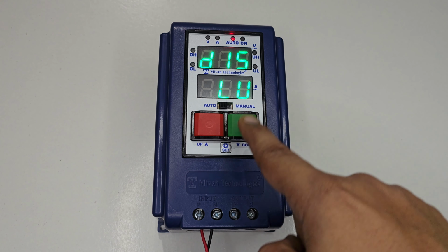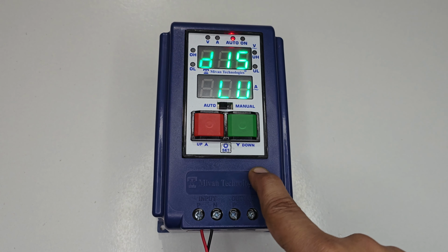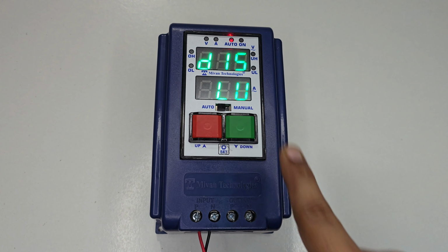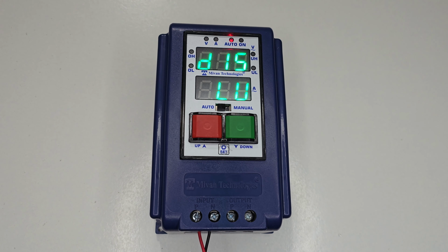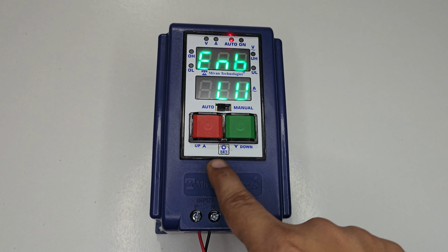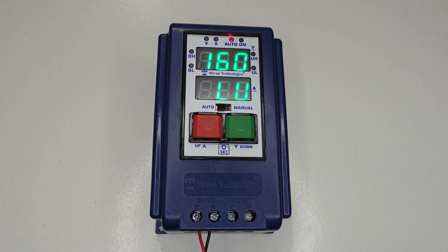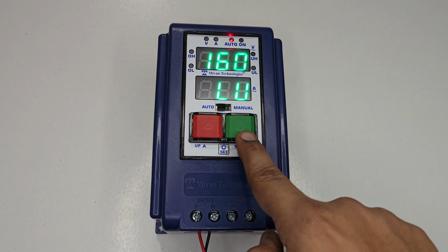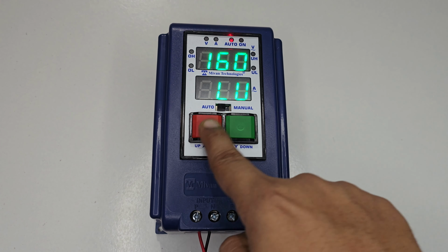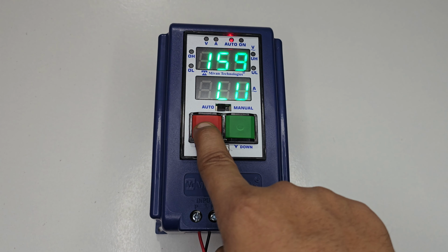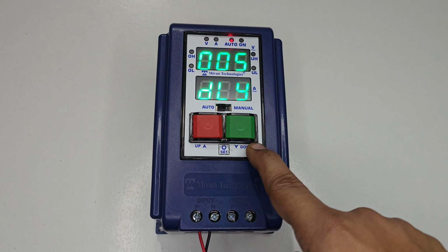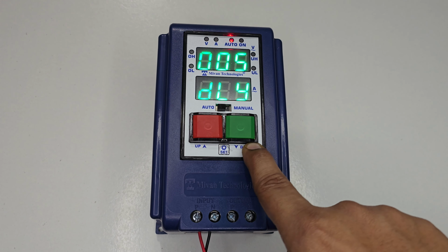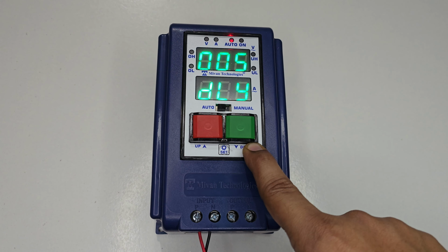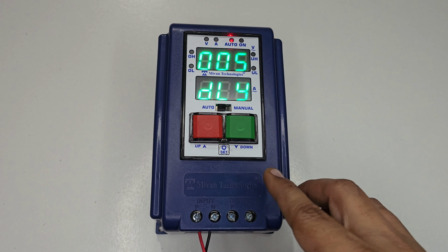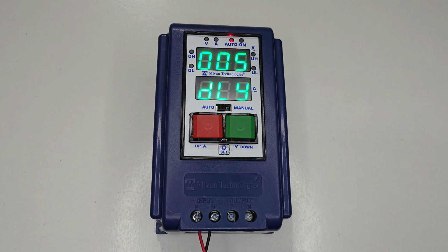When you press the set button, here low voltage enable disable option comes. By pressing up and down key, you can enable and disable the low voltage protection. Make it enable, press the set button. Here you can adjust the low voltage cutoff limit. By pressing up and down key, you can adjust the low voltage cutoff limit. Press the set button to store the value. This is a delayed time. Delayed time means once the voltage goes high or low beyond the cutoff limit, it will trip the motor after 5 seconds. That seconds you can adjust in minutes.